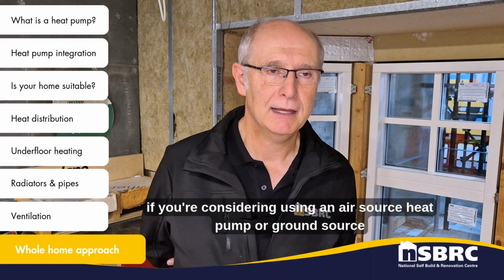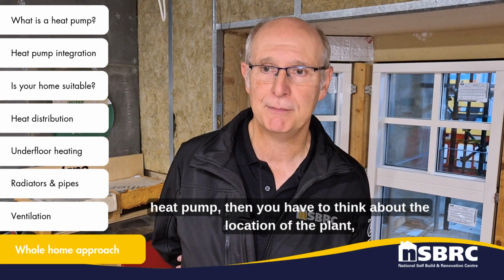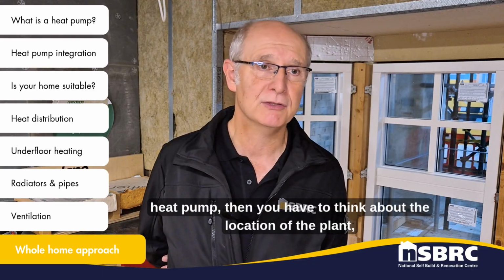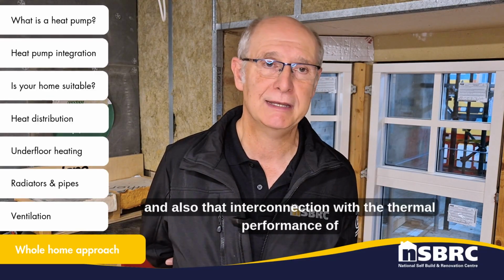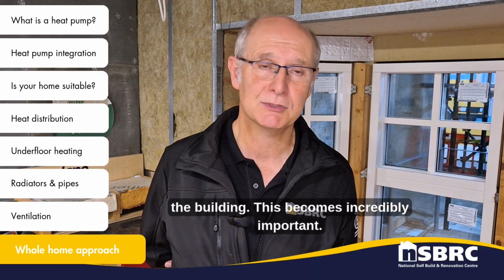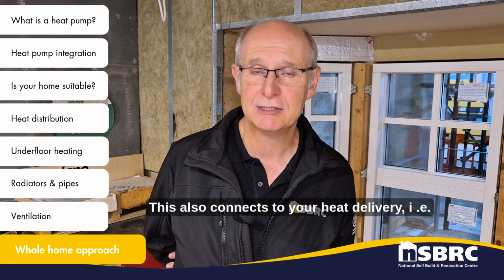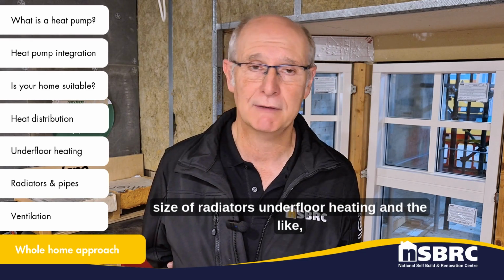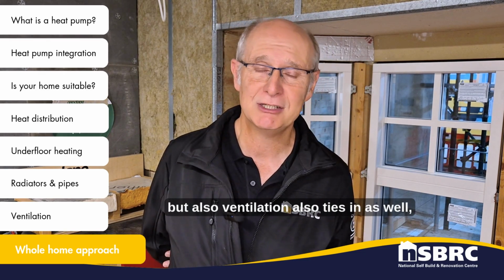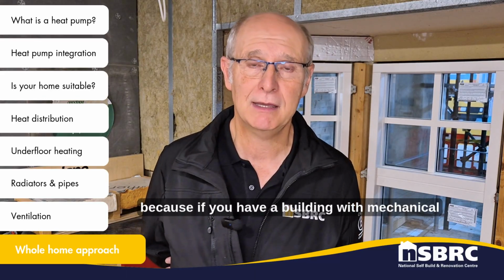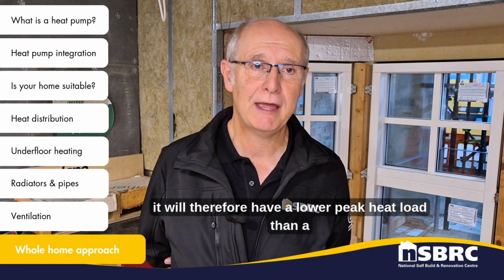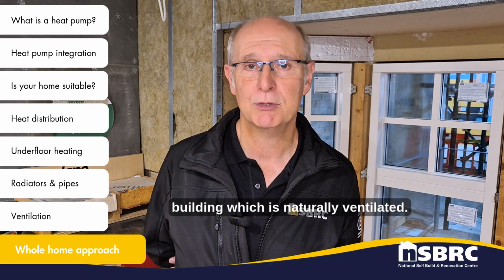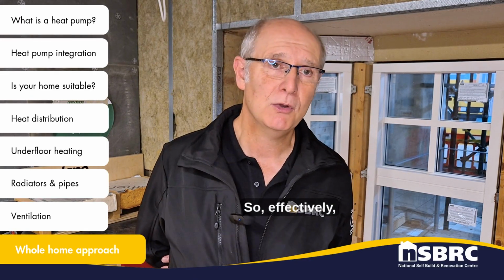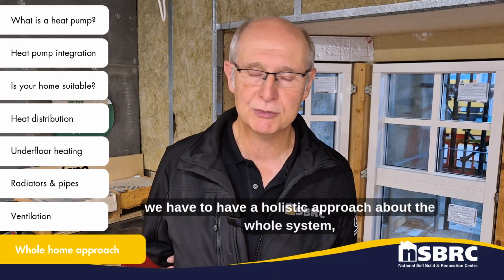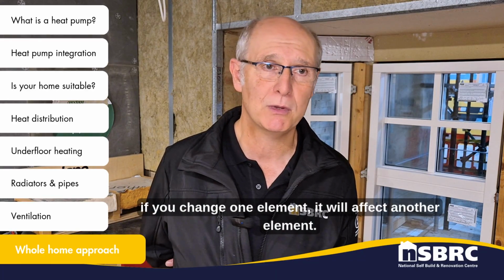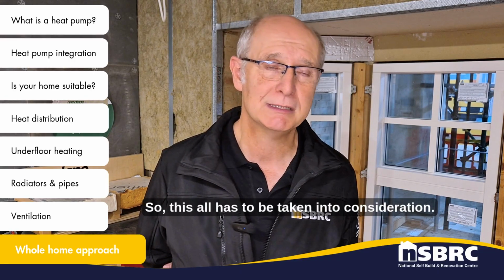So, in summary, if you're considering using an air source heat pump or ground source heat pump, then you have to think about the location of the plant, the peak heat load, and also that in connection with the thermal performance of the building. This becomes incredibly important. This also connects to your heat delivery, i.e. size of radiators and floor heating and the like, but ventilation also ties in as well, because if you have a building with mechanical ventilation, it will therefore have a lower peak heat load than a building which is naturally ventilated. So effectively, we have to have a holistic approach about the whole system, because if you change one element, it will affect another element. So this all has to be taken into consideration.